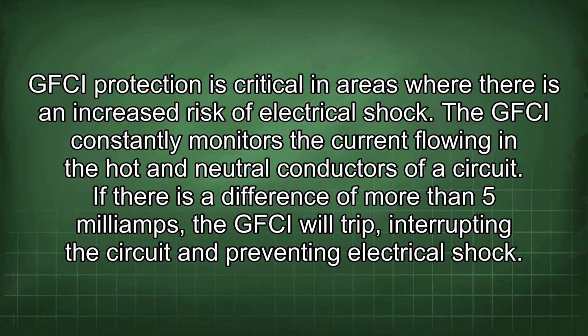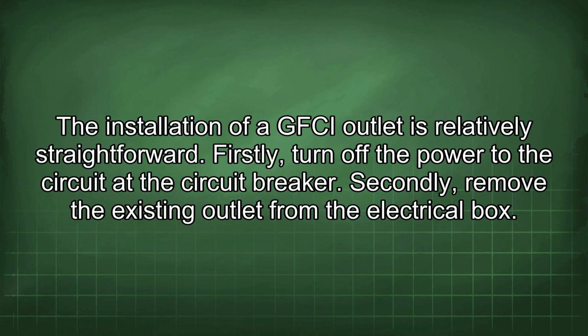GFCI protection is critical in areas where there is an increased risk of electrical shock. The GFCI constantly monitors the current flowing in the hot and neutral conductors of a circuit. If there is a difference of more than 5 mA, the GFCI will trip, interrupting the circuit and preventing electrical shock. The installation of a GFCI outlet is relatively straightforward.